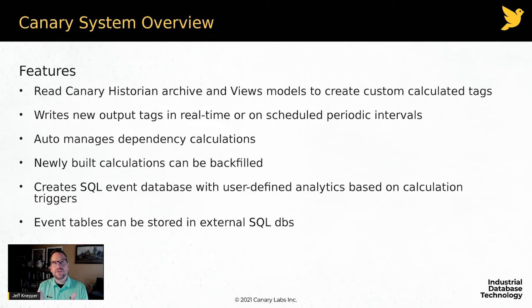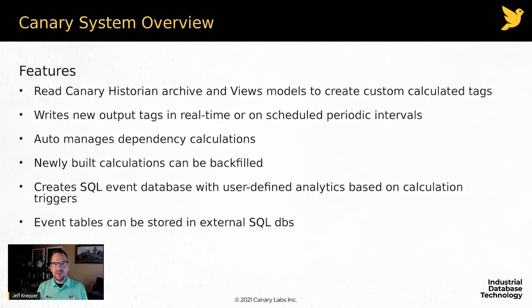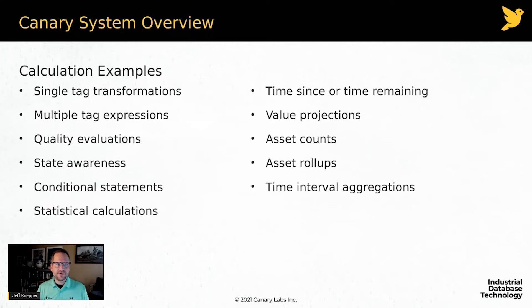As you're building calculations, at some point you'll build one that serves as a notification, alarm, or boolean that is true or false, representing an event frame — something has started. We can monitor that process and create a separate SQL table of events. You define the start, define the stop, and in between is the duration of your event. That event gets linked to the asset it belongs to, and within that duration you can create custom analytics and new analytic tags or properties around the event itself.